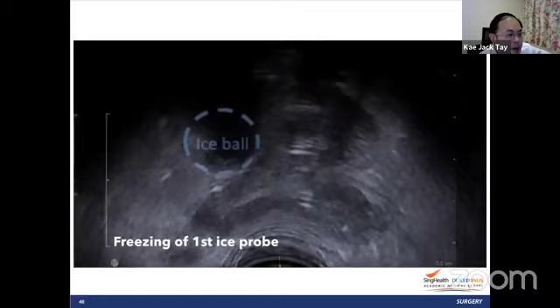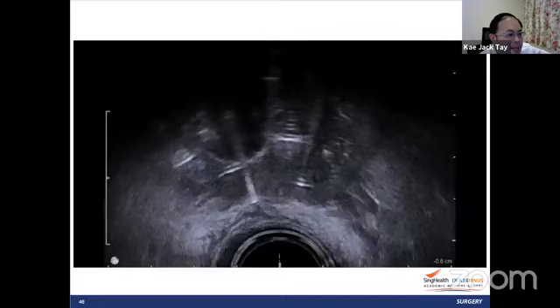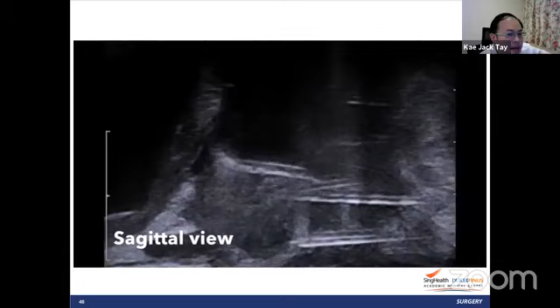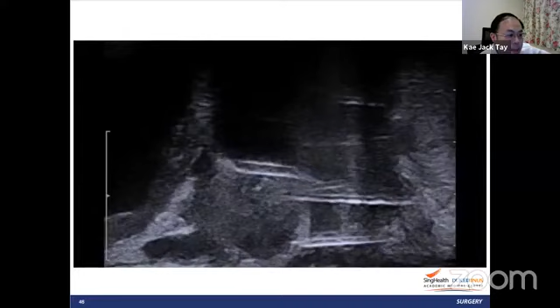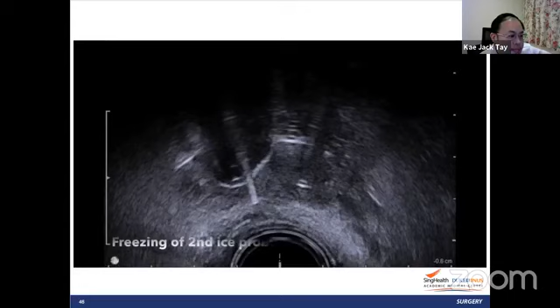And here's us treating the patient. You can see that ice ball forming in the first cryoprobe. And as it gets near the second probe, remember we put 2 on the right side, we will start the freezing there. So you can see on the sagittal view, you can see that ice ball there. So the ice edge, which is at 0 degrees, actually it's non-lethal because you need to go about 5 mm behind the 0 degree ice edge to be where the lethal temperature is, and that's anything less than -20. So this, we start freezing with the second probe, and you can see that that kind of supercharges it.